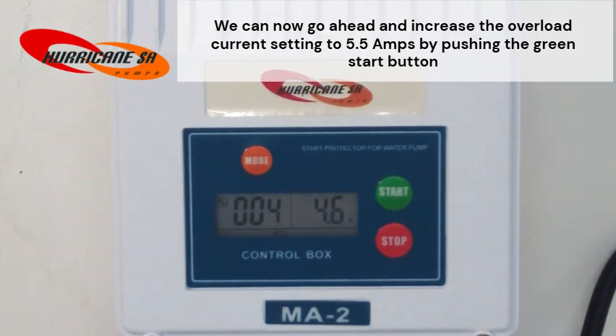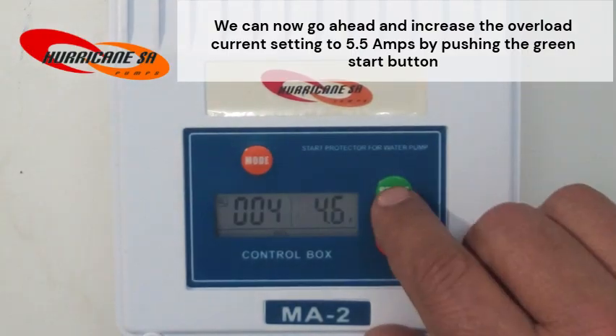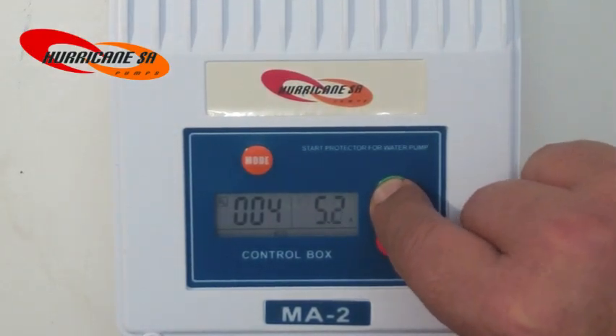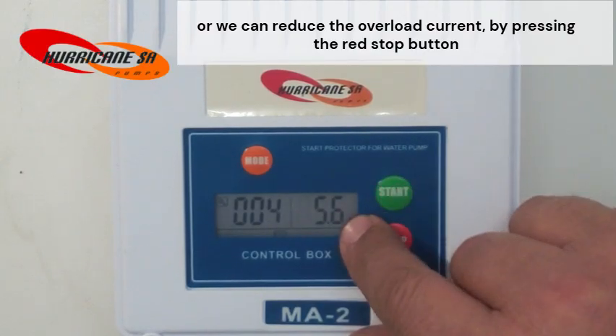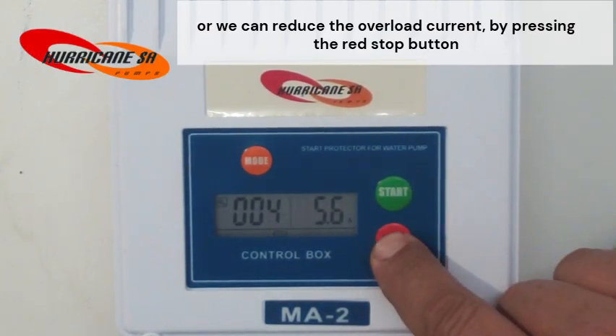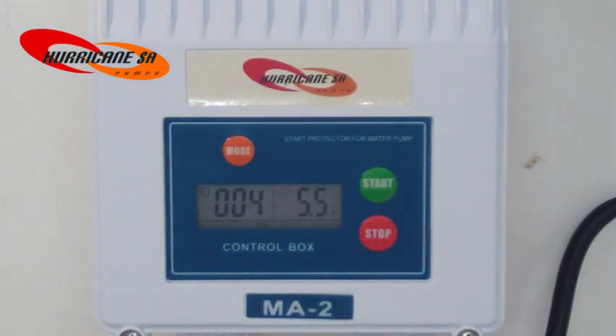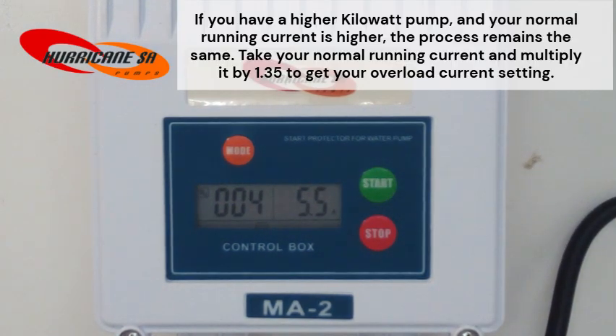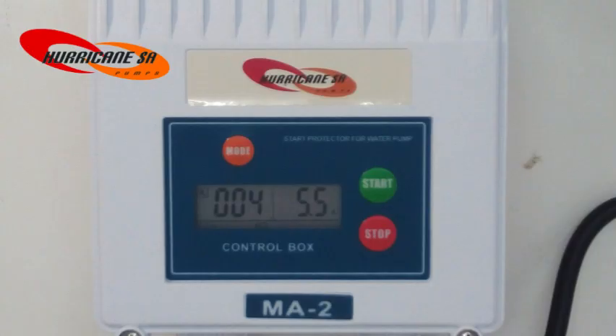We can now go ahead and increase the overload current setting to 5.5 amps by pushing the green start button. Or we can reduce the overload current by pressing the red stop button. If you have a higher kilowatt pump and your normal running current is higher, the process remains the same. Take your normal running current and multiply it by 1.35 to get your overload current setting.